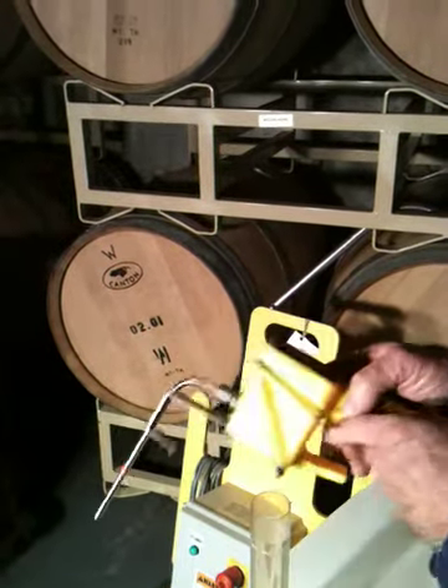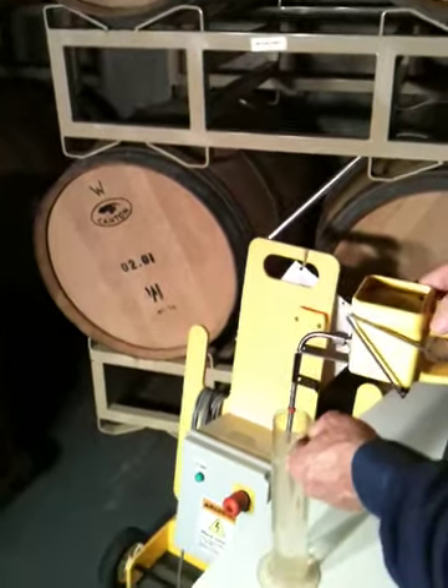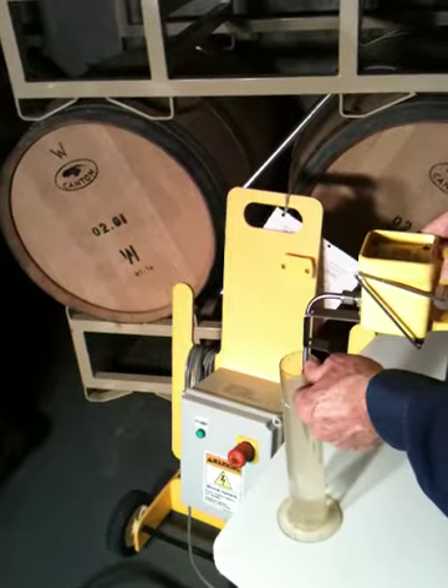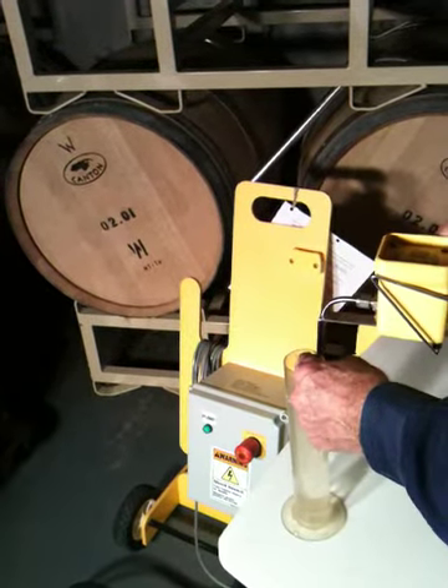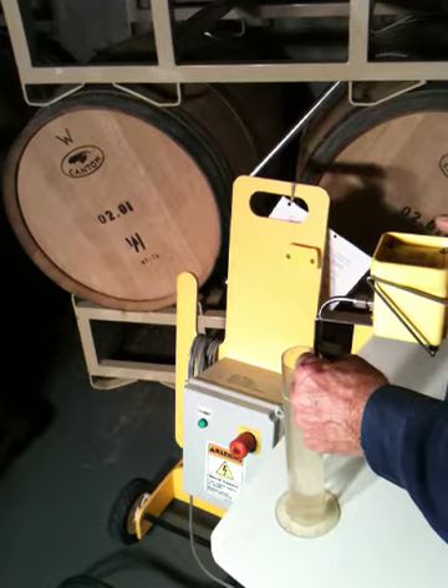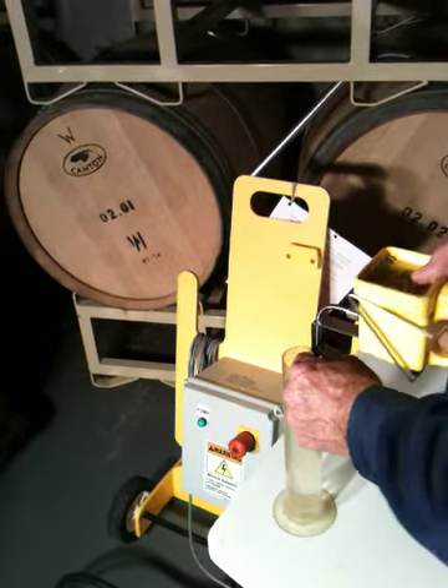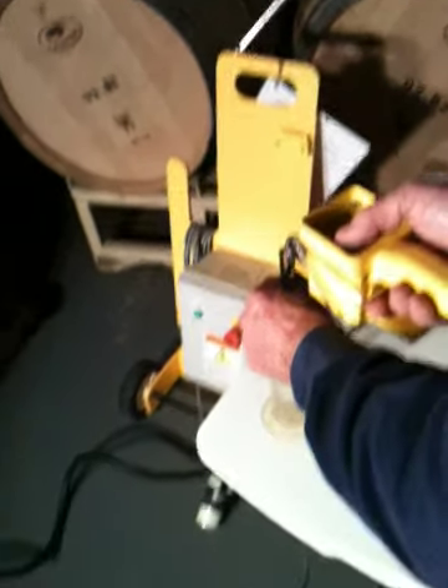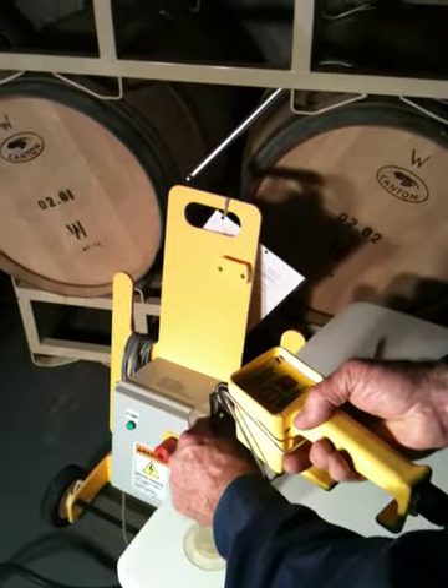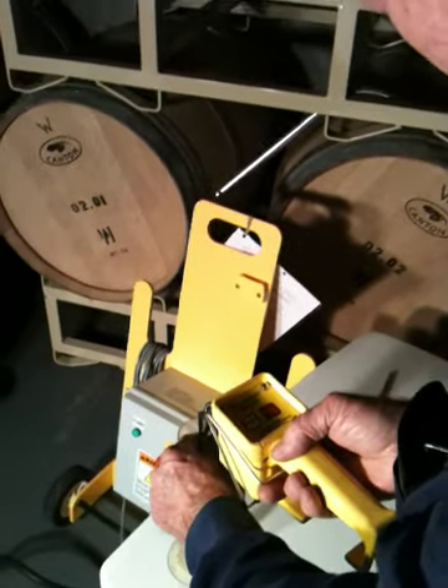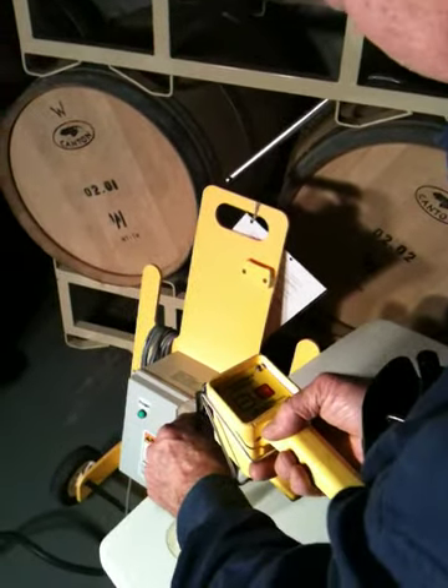So now we want to immerse the sensor tube back down into at least 2 inches of liquid. And in this test, you've got to hold the tube steady. You can't go up or down. You hold it not moving. And now you press the start button. And when you do, it's going to alternate. The LED light is alternating between green and red, letting you know it's in the testing mode.